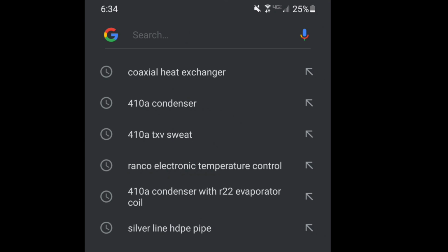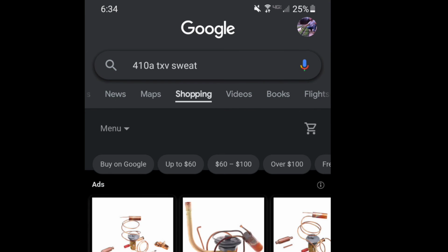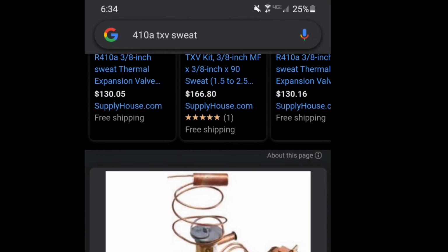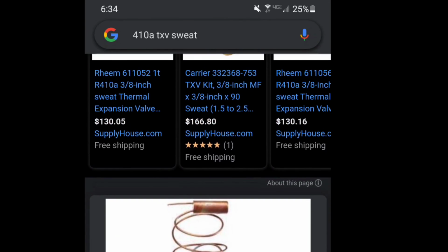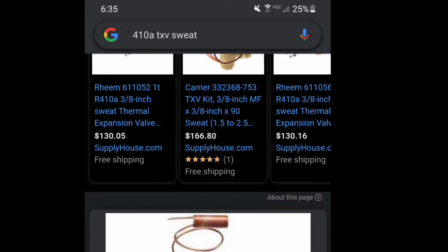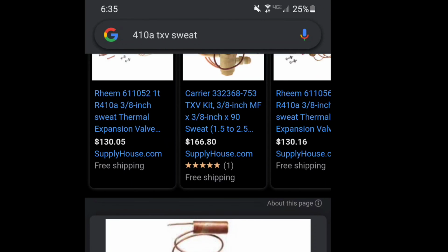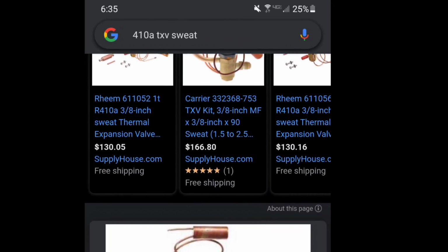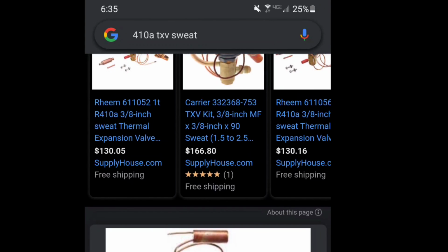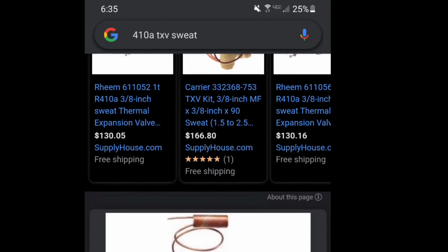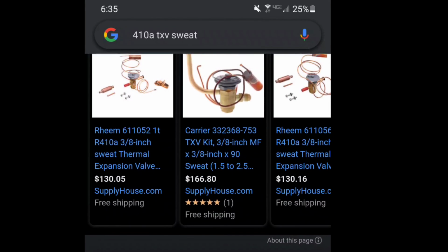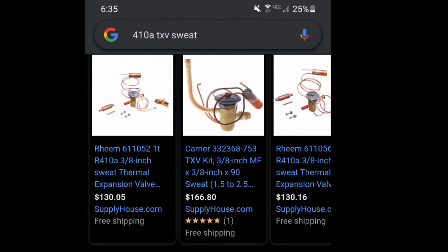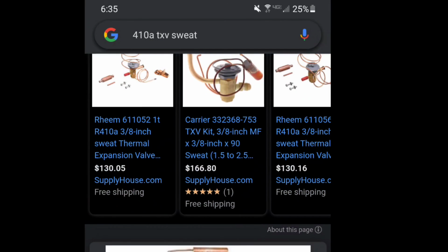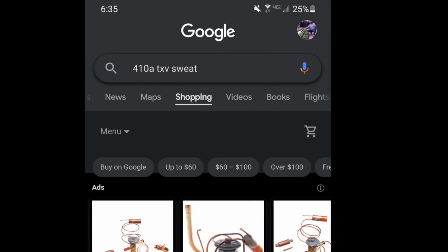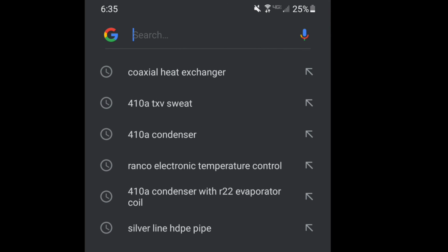Let's move on to the 410A TXV. Why do you need a TXV? Without it, you can't properly meter the refrigerant going into the coaxial. Make sure your equalizer tube, a little bitty line smaller than 1/4 inch, more like 1/8 inch, is soldered into the suction line going into your coaxial. Then you need a bulb mounted right next to it on the vapor line going into the coaxial. That's the sweat-on thermal expansion valve, which meters the refrigerant. If you don't have it, it won't work properly.